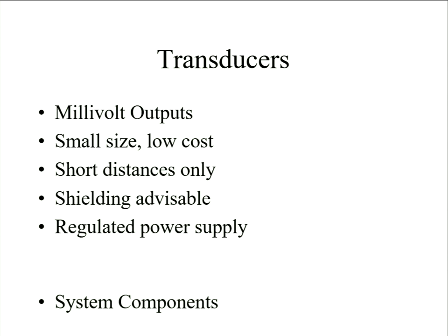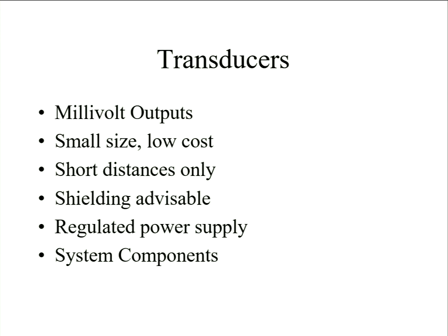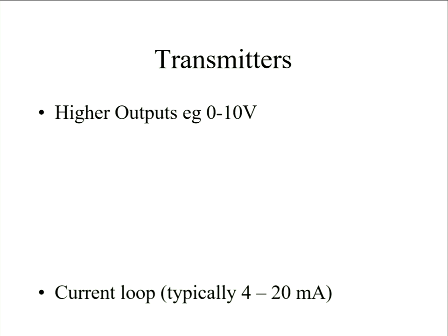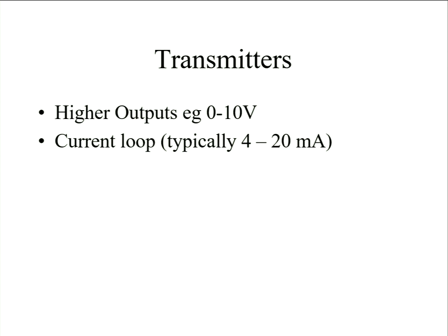But the thing is, they tend to be bigger, beefier things, higher cost. They may have local digital readings. I think most terminals I've walked around have an LCD display on them, so you don't have to radio back to the control room to find what it's reading. You can read it yourself locally as well. But again, there's an element of cost in there. So the advantage is that it's not particularly affected by the resistance of the connecting wires, so you can operate over long cables. That provides the power to the transmitter. And I'd say the Live Zero is certainly an advantage, and a bit more noise immunity.